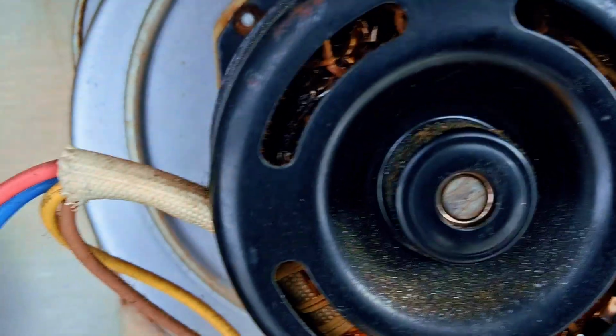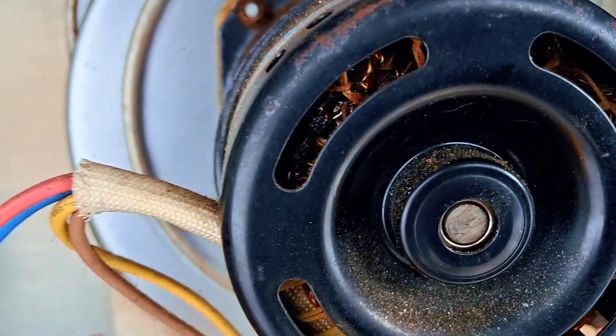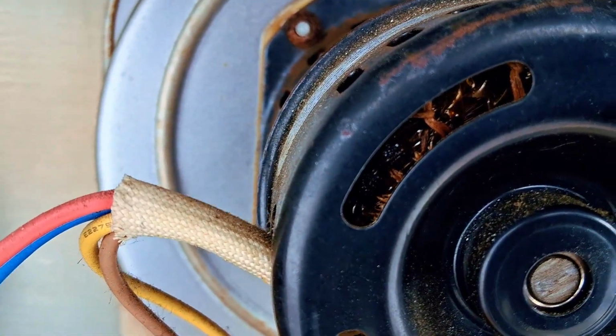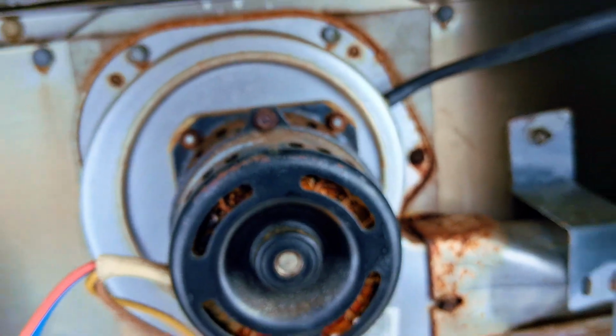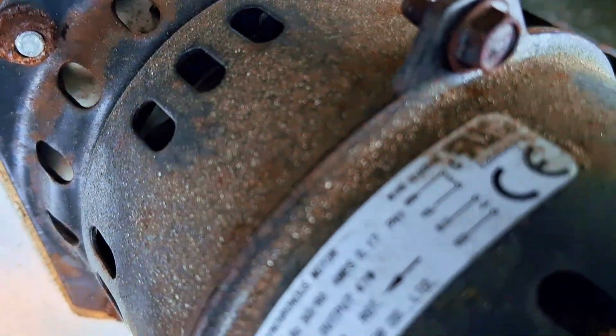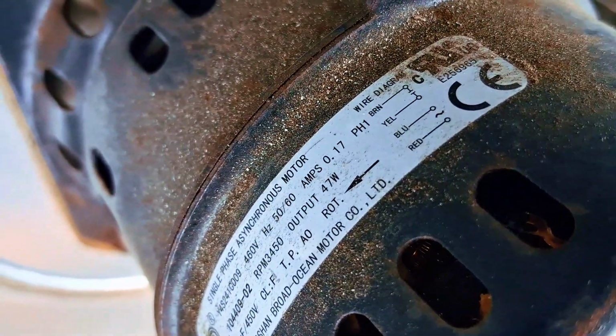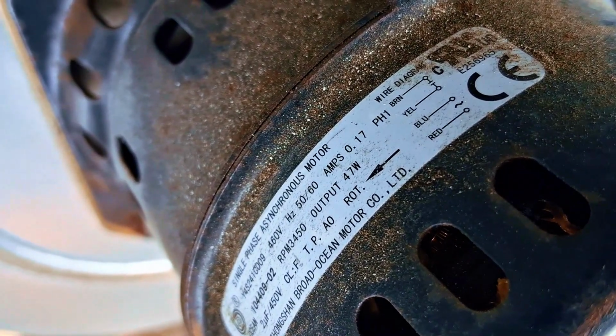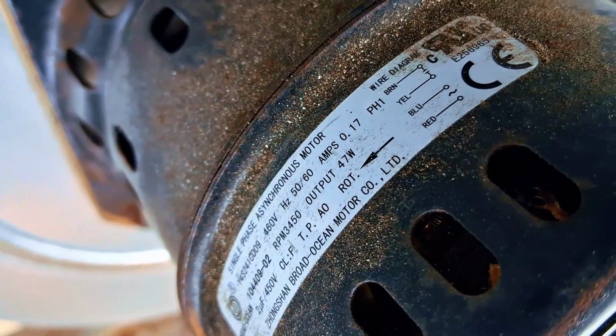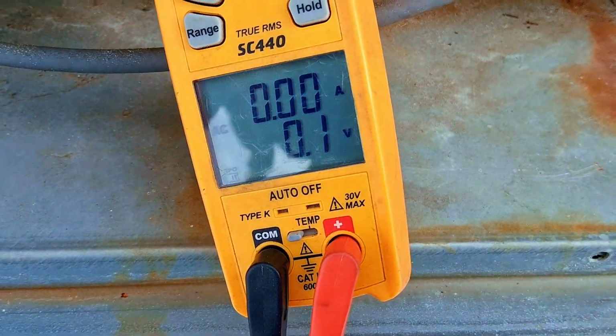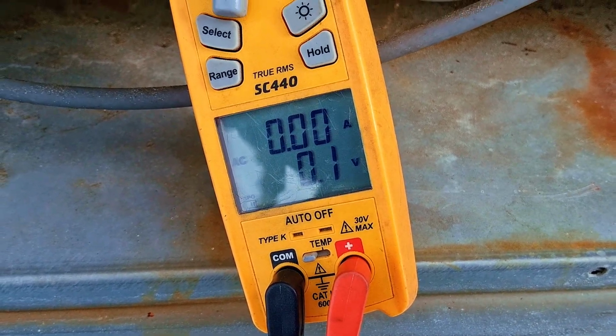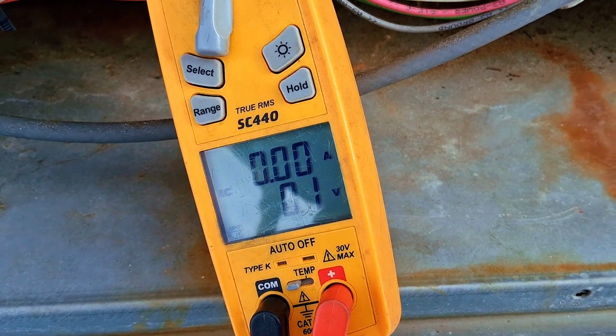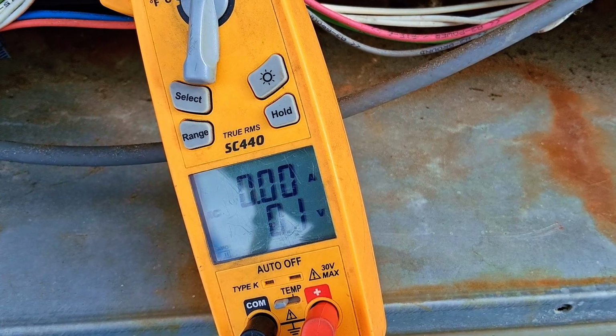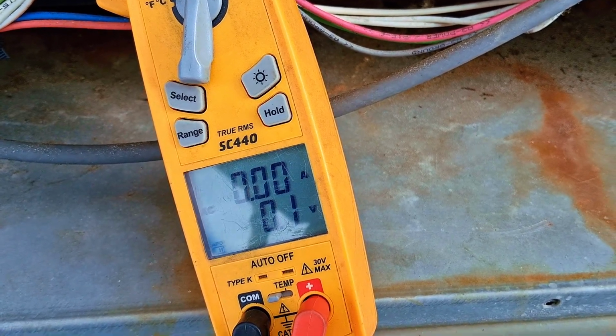You can see here, the back of the coil and inducer is burnt out. Once it comes back on, I can show you guys the amps. You see the amps here is rated 0.17 for amps, and when it came on, I was getting like 1 point something in amps. So this inducer motor is dropping out, which is killing the pressure switch.